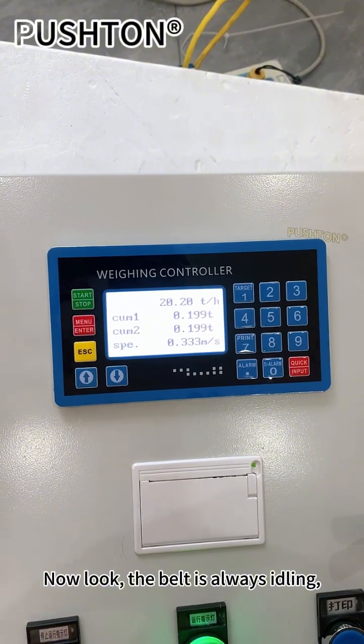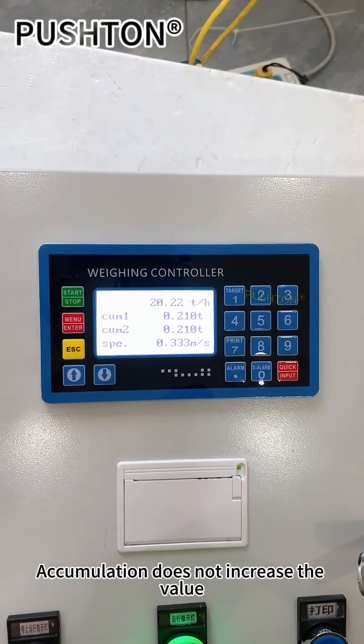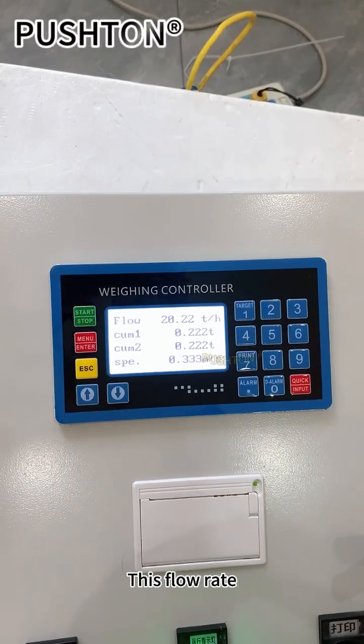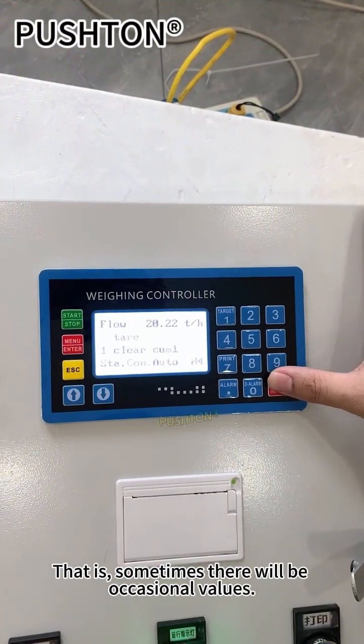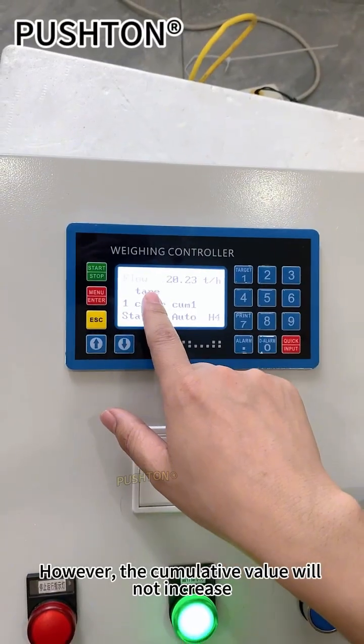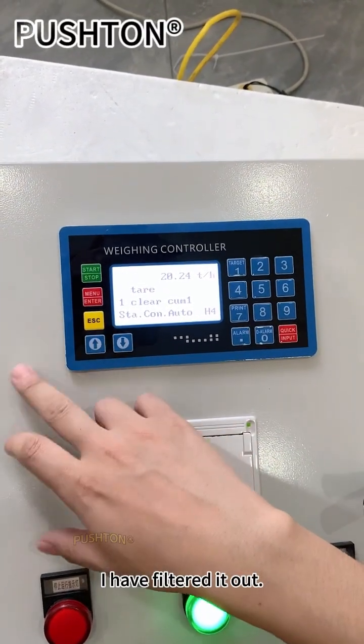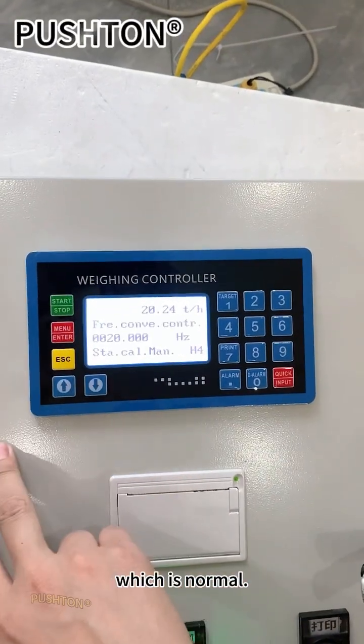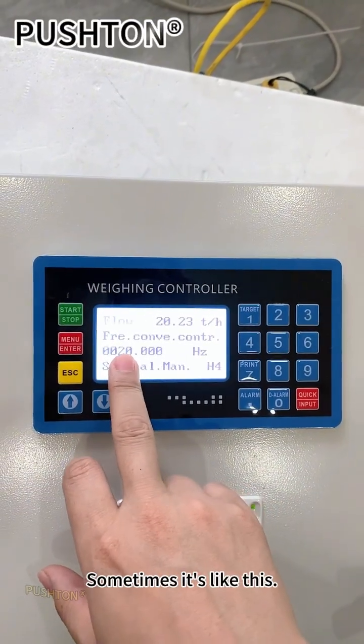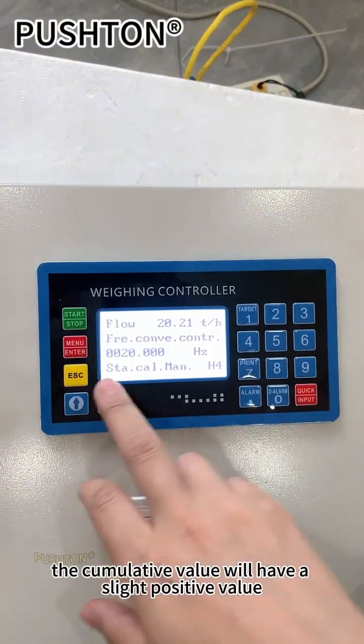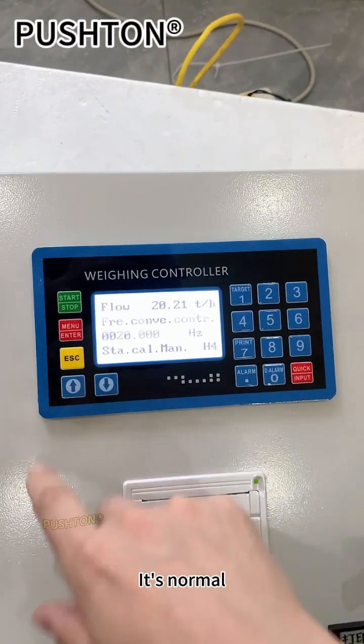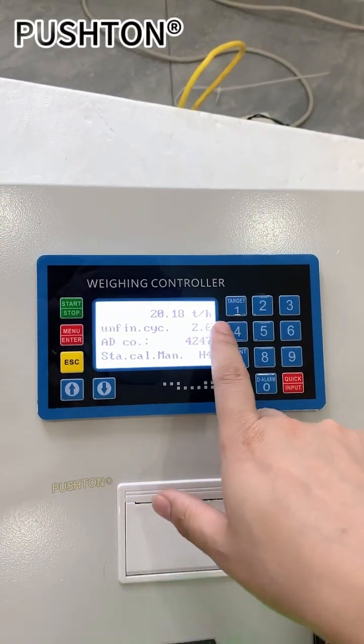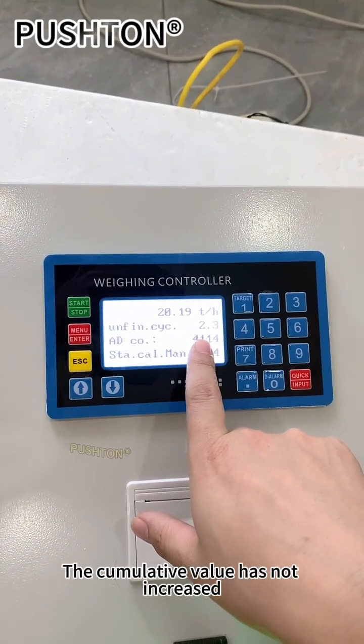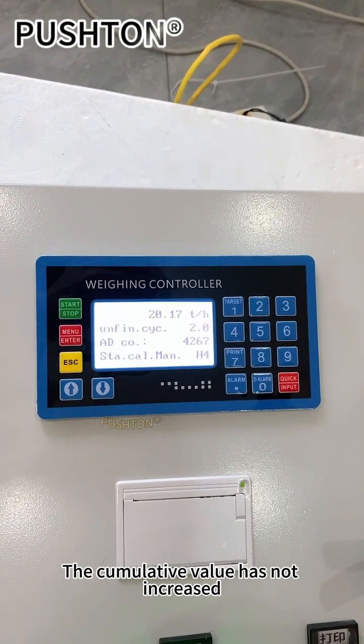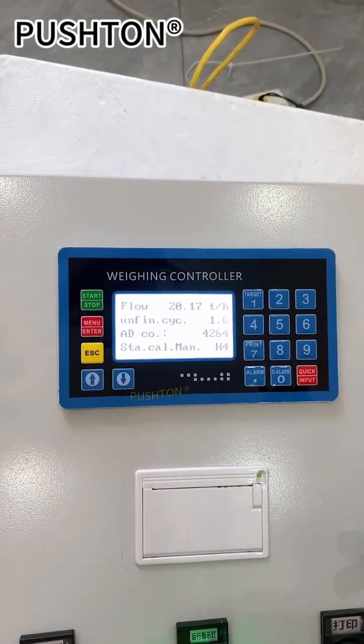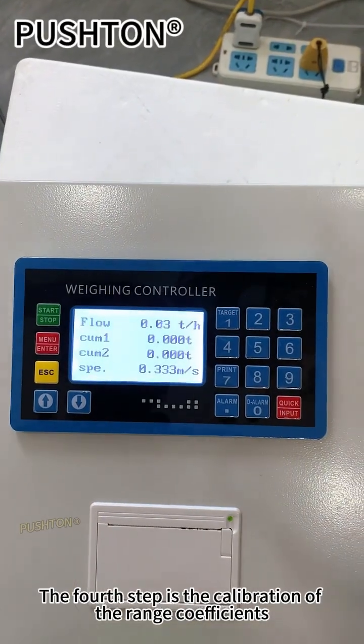Now look, the belt is always idling. Accumulation does not increase in value. This flow rate sometimes shows occasional values. However, the cumulative value will not increase. I have filtered it out. It doesn't matter, which is normal. Sometimes the cumulative value will have a slight positive value. It's normal. And negative fluctuations. There has been no fluctuation now. The cumulative value has not increased. Clearing has been completed.